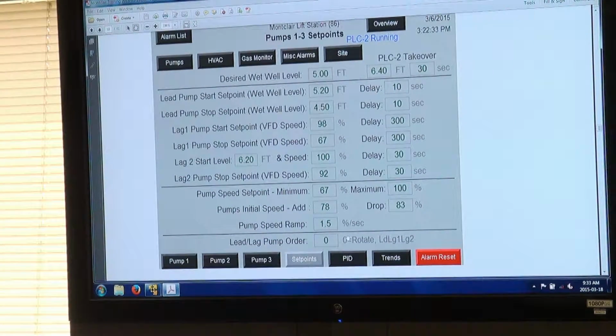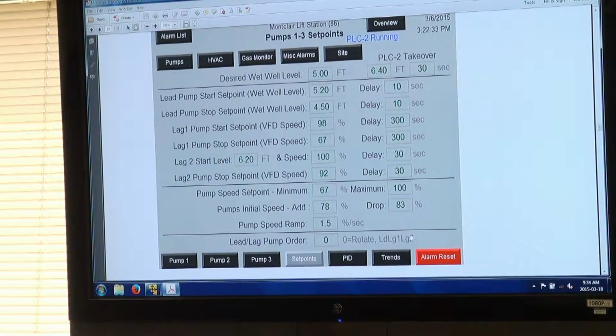If you have currently pump 1 running and you go from 0 to 1, 2, 3, nothing will happen. But if pump 1's the only pump running and I change my order to 2, 3, 1, pump 1 is going to stop right there and pump 2 is going to start. If you do have a fixed order and the first pump is not available, then you will go to the second pump automatically. But when that first pump does become available, we'll stop and start the other at the same time.